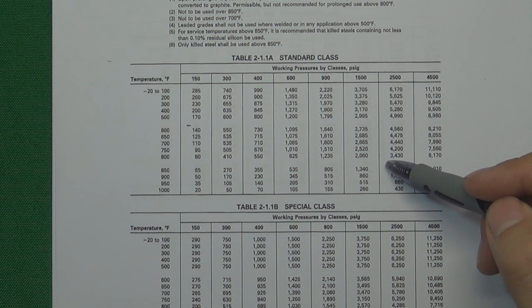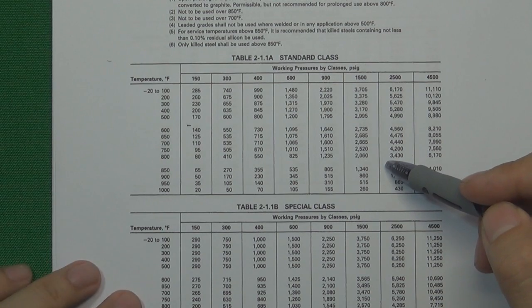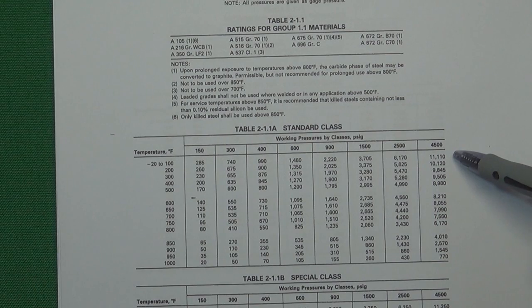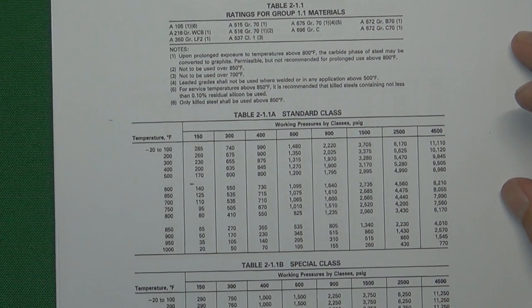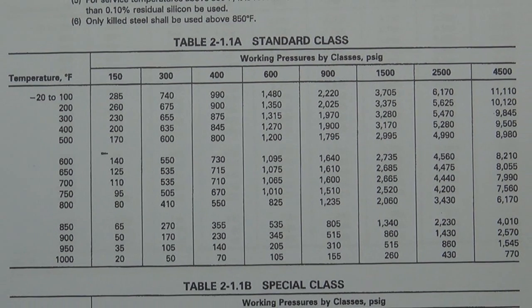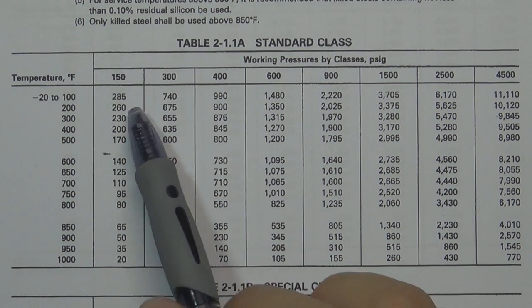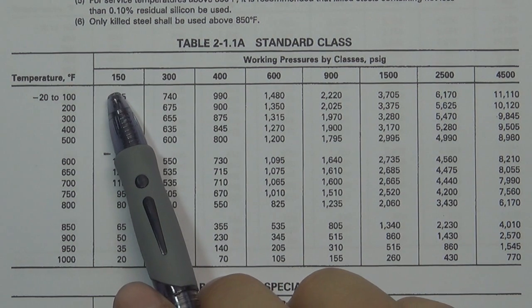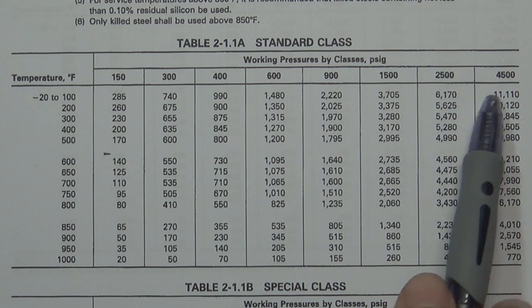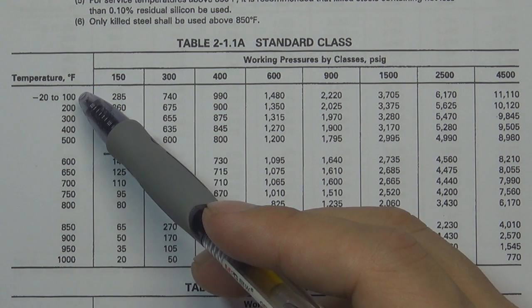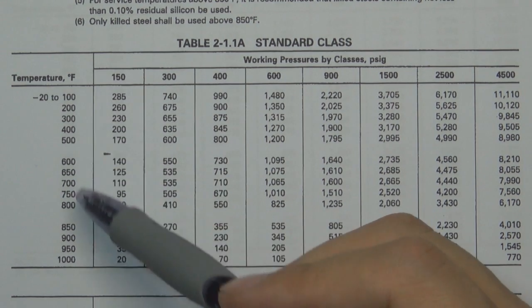When looking at the pressure-temperature reading table, consider two things: first, the material; second, the connection type. Then you can find the correct table to use. In the table, the horizontal axis is divided into different pressure classes from 150 to 4500, and the vertical axis is divided into different temperature ranges from 100 to 1000.